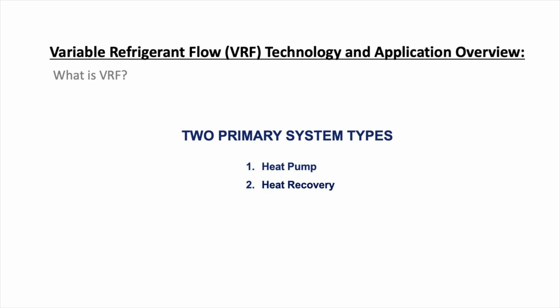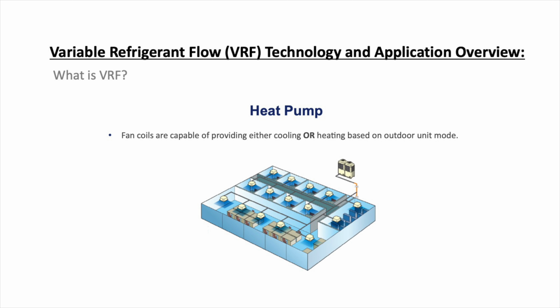Now, there are two different types of VRF. You have heat pump and you have heat recovery. In a heat pump system, fan coils are capable of providing either cooling or heating based on the outdoor unit mode. So if one zone calls for cooling, then the entire system can only be in cooling. And likewise, if a zone calls for heating, then the entire system is in heating mode only.